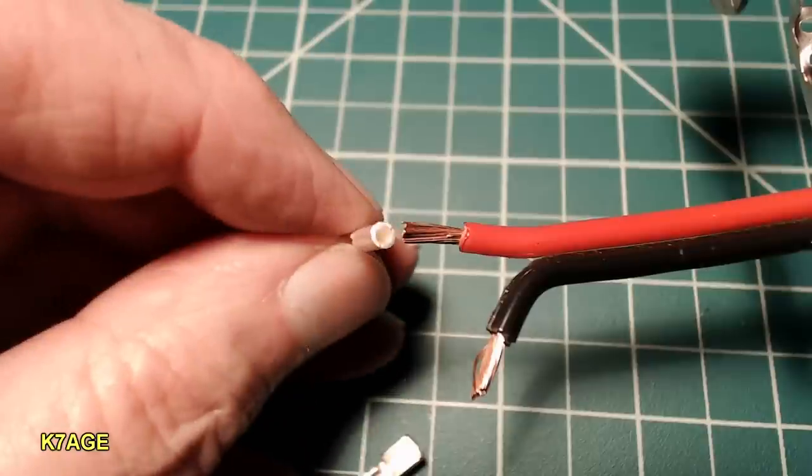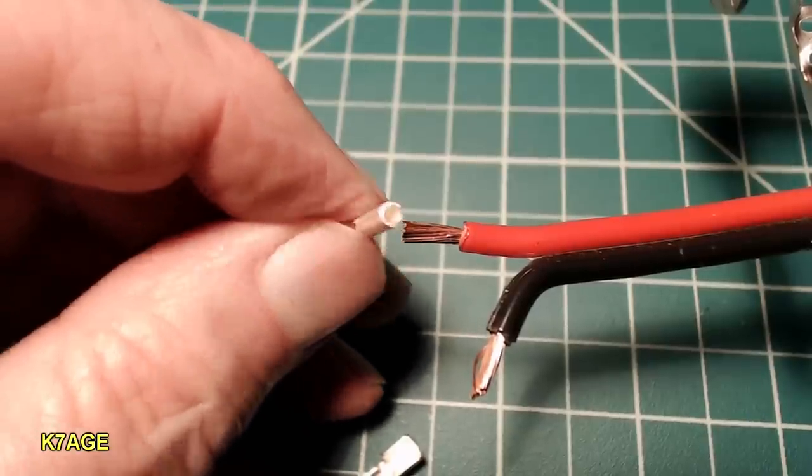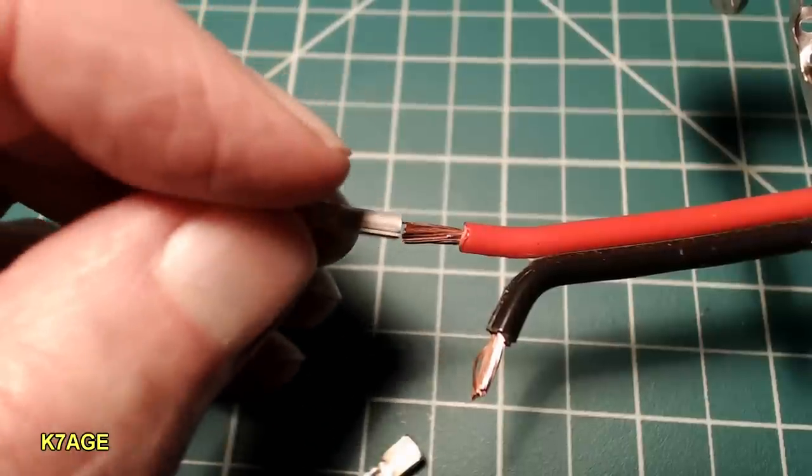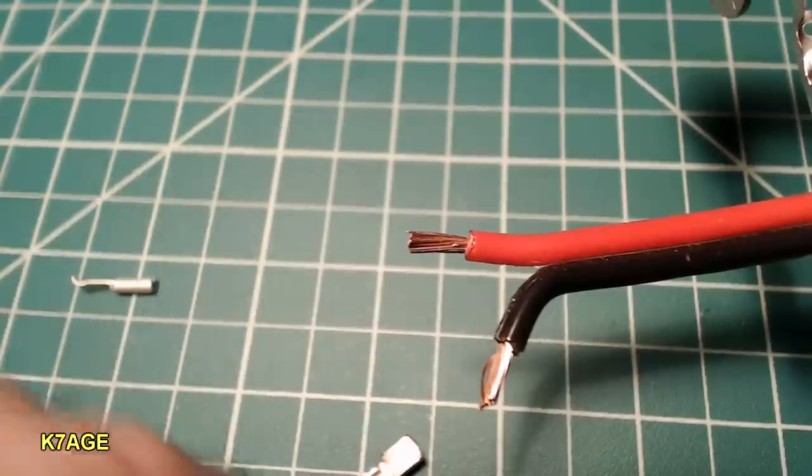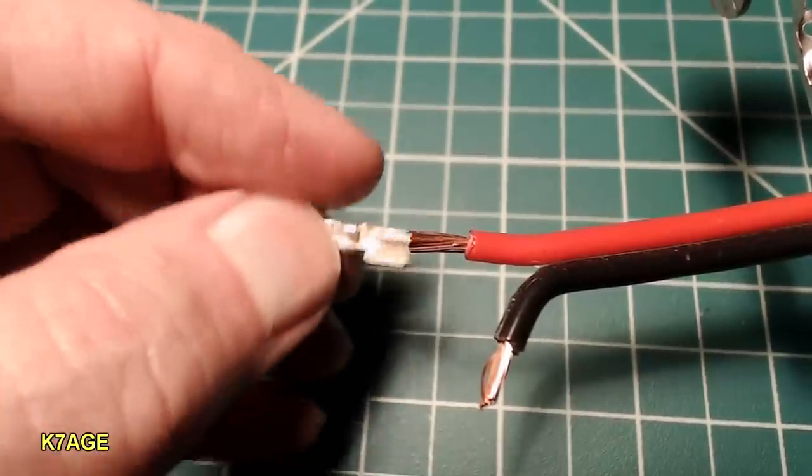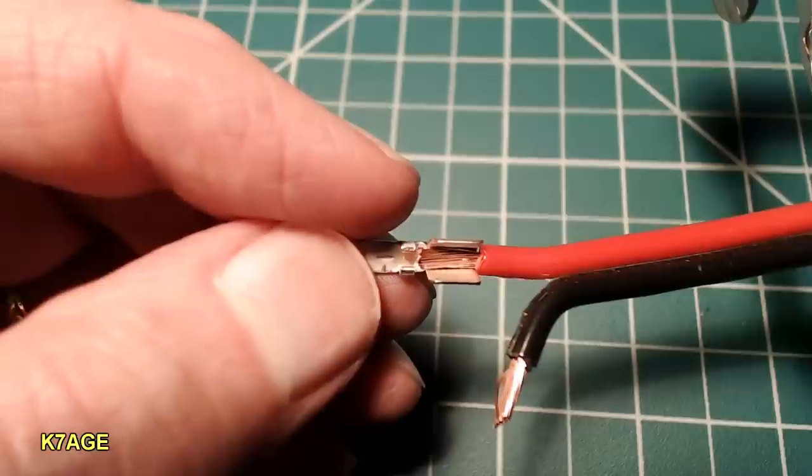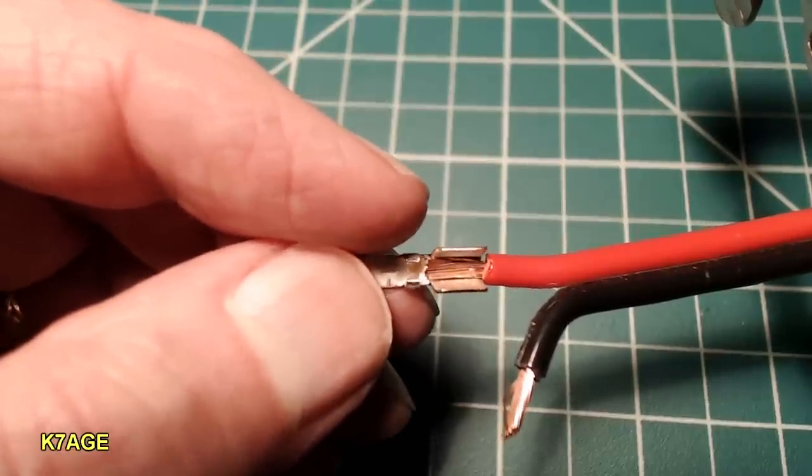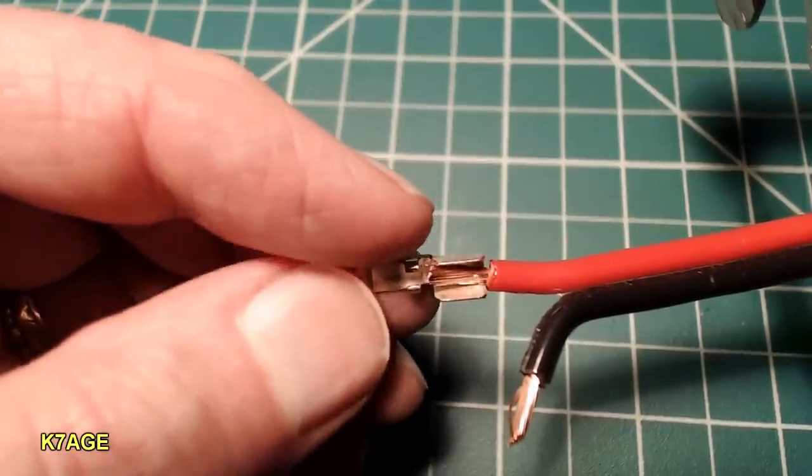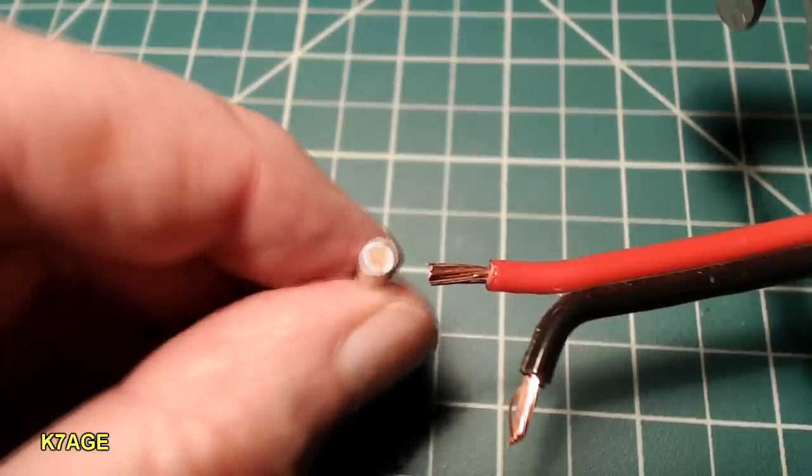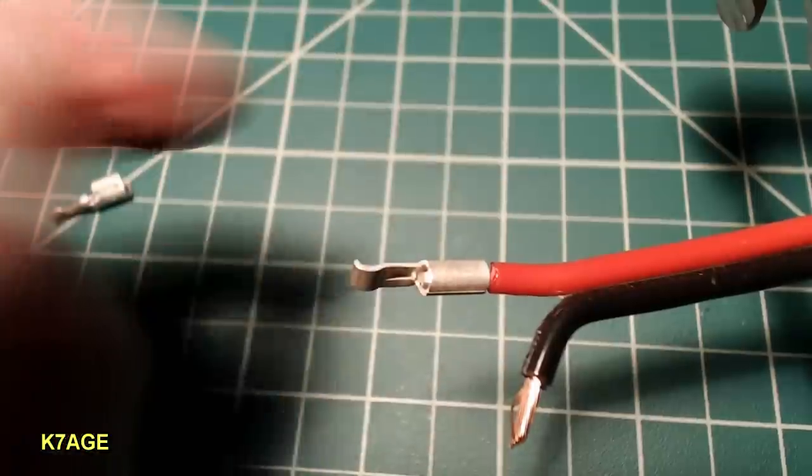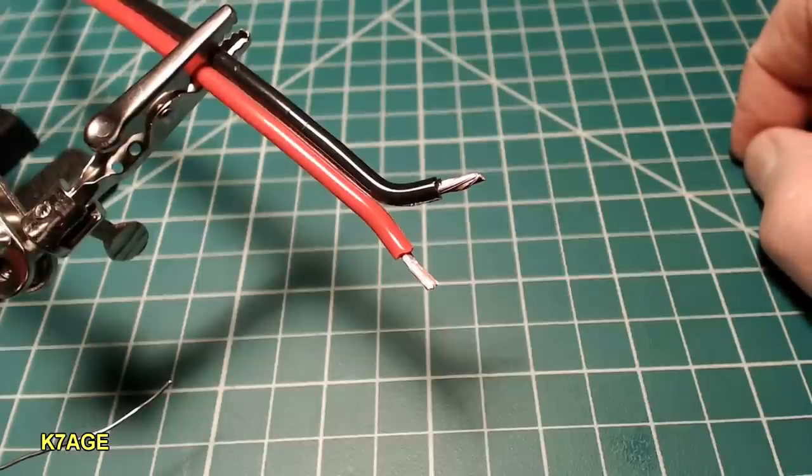First one is the 15 amp. And you can see the wire diameter is larger than the center of the pin. And it won't go on. That's the 15. This is the 45. And this would probably work. It's quite a bit large. And if I solder this, I have to bend the tabs over myself. So that's the 45. And here's the 30 amp pin. You can see that looks about right. And this slides over the wire easily. So we'll use the 30 amp pin.